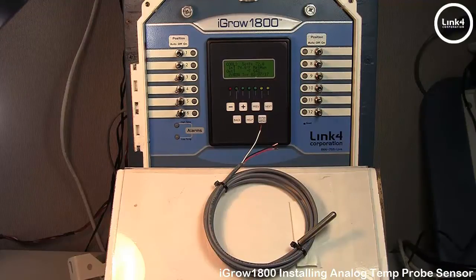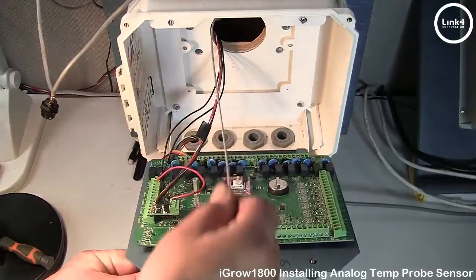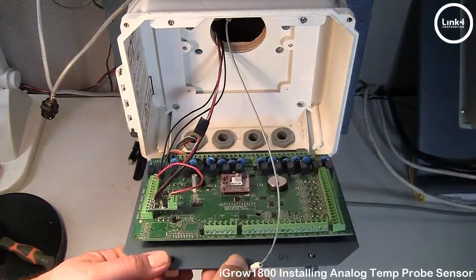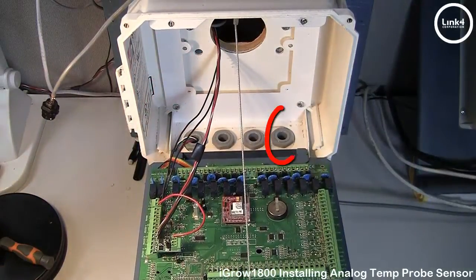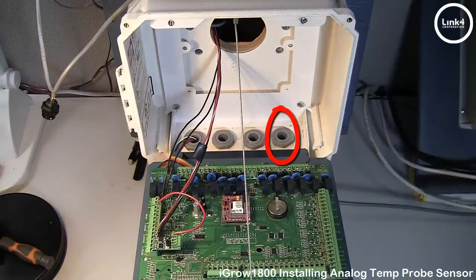Note, if any splices are needed to extend the cable length, make sure the splice is watertight, because water or fertilizer infiltration will cause unstable sensor readings. Now, to install, you want to power down the controller and open the front panel to the 90-degree position. Next, carefully insert the cable through the rightmost watertight fitting at the bottom of the enclosure.